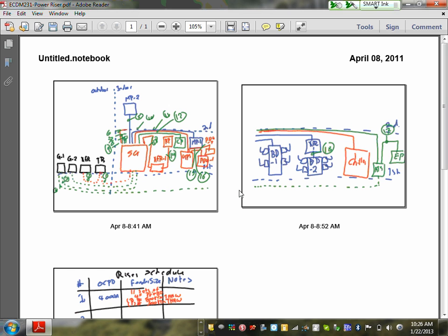Well, what I'm talking about, I don't need to draw yet, but basically on a breaker, if you want it electrically operated so you can remotely control it to open and close it, all we need to do is add a shunt close coil and a shunt open coil and then a spring charging motor. All that spring charging motor does is, you only get so many operations out of a charge. I said you had to pump the breaker up because it's got internal springs. An open, close, open, at that point the spring would be discharged, and you can't operate the breaker again until you charge that spring.